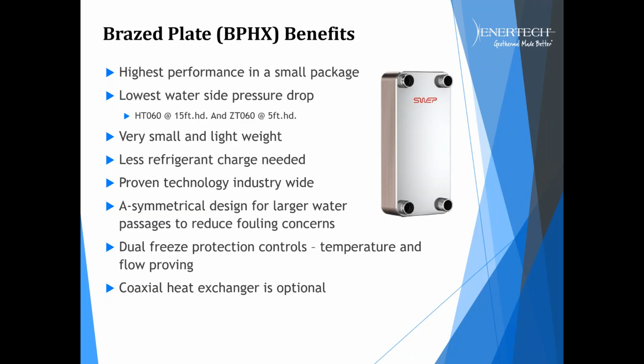Okay, obviously it's very small, very lightweight. Actually, the direct comparison to a coax of similar size would be about 70 pounds lighter. We've also got less refrigerant volume needed within this heat exchanger, and paired with the microchannel, now we've got a balanced charge between heating and cooling, whereas with the coax we did not have a balanced charge. So then we needed to add a charge compensator from switching from heating to cooling to balance out that charge. So this is also a nice benefit. It is proven technology. It's been used industry-wide for all different applications, but this particular heat exchanger is a little bit different. It's what we call asymmetrical, and I'll show you a slide here what that means, but it really just helps us alleviate any of those freeze issues and fouling issues.